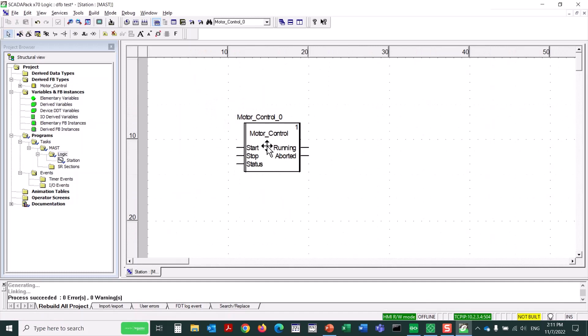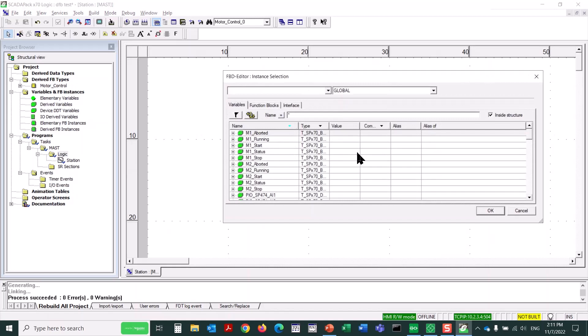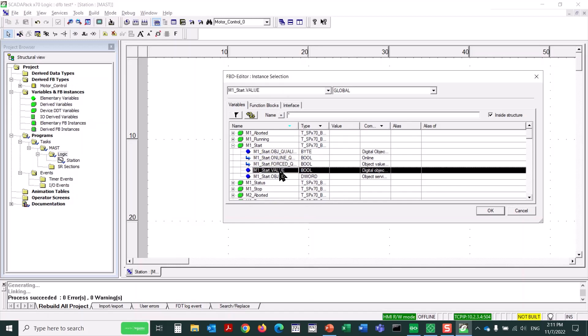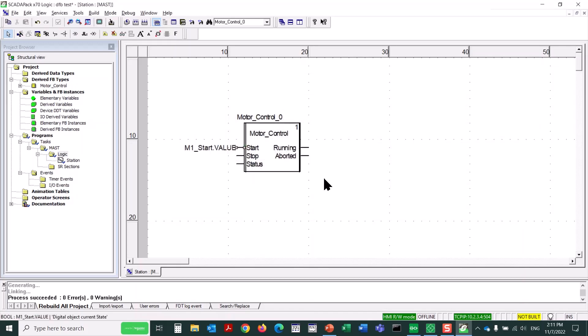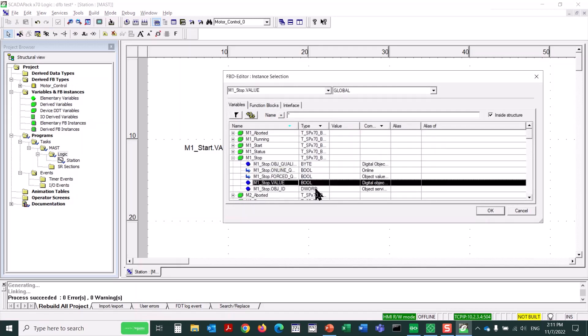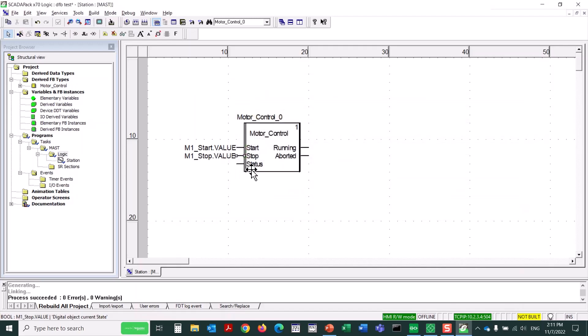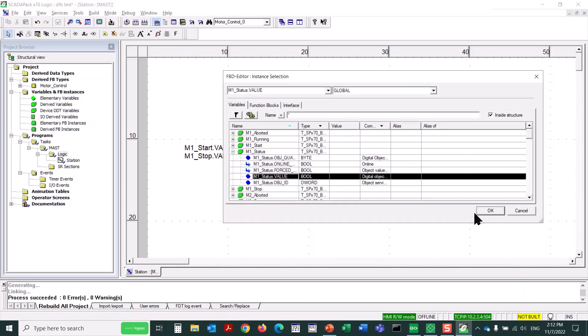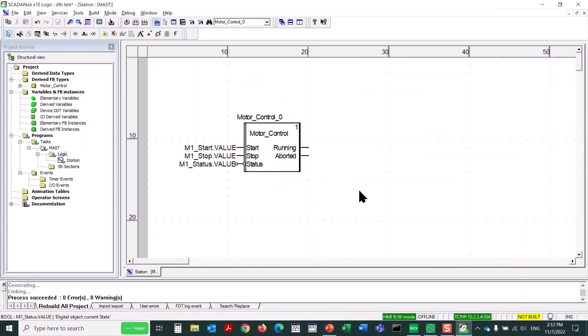So now I'm going to simply double-click on the Start Input pin. Use the Ellipsis button. And I want to pick M1 Start. But not just M1 Start itself. That is the overall object. But we'll click the plus to expand the object. And you can see various parameters. We want the dot value subparameter of this object. Then we'll do the same with Stop. And it's going to be M1 Stop dot value. And we'll do the same with Status. The dot value parameter.